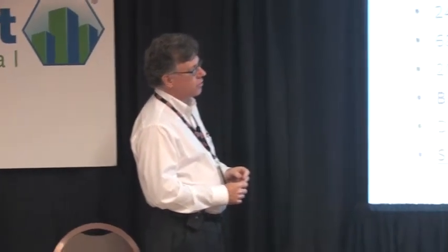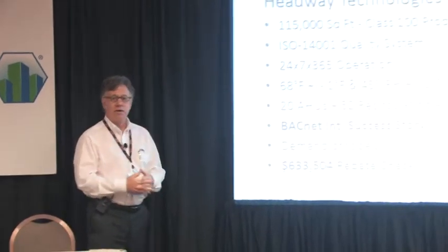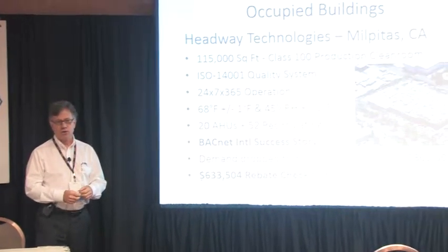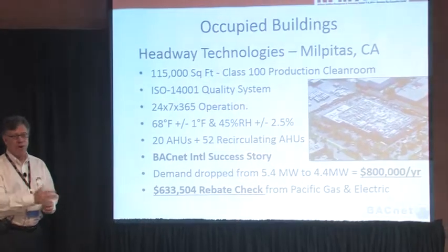The problem with that is they can't shut down anything. That facility has to be running 24/7, 365. It never shuts down. It doesn't shut down for Christmas. It doesn't shut down for New Year's. It shuts down for nothing. So it became a very, very difficult conversion process because they could not turn off an air handling unit for more than just a couple of minutes to go from pneumatic to digital.